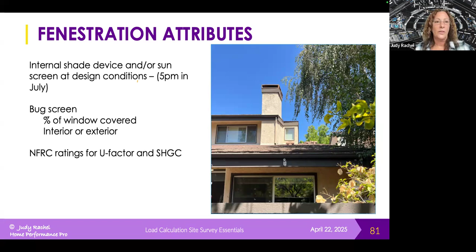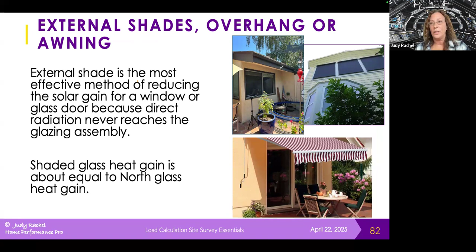Then there are external shades, overhangs, and awnings. We talked about how latitude affects how well overhangs and awnings shade windows, so we need to measure them. We measure the horizontal projection, from the wall to the lowest part of the overhang, and the vertical separation, from the top of the window to the lowest part of the overhang. That vertical separation can be one of the most difficult measurements to make in the field.